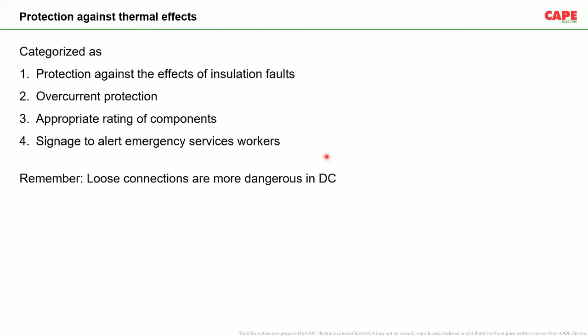The protective measures against thermal effects are classified into protection against the effect of insulation fault, overcurrent protection, appropriate rating of components, and signage to alert emergency service workers. These are the recommended protective measures against thermal effect. Number one, protection against the effect of insulation fault. That means in case of any insulation fault, you do something so that the solar PV does not catch fire.